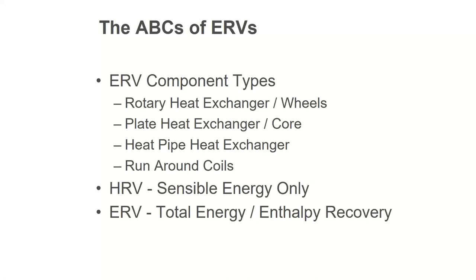So there are two types. There's HRV and ERV. HRV is heat recovery ventilator, sensible only energy, no latent. Latent's not my problem. I don't do moisture. Then there's ERV, enthalpy recovery ventilator. I do sensible plus latent energy. So obviously I want to do both when I can. There are some projects where you're going to want to do the HRV. Those projects are ones where the indoor humidity is regularly worse than the outdoor humidity. What do I mean by that? Well, if you're doing a locker room at a fitness center, you're generating a lot of water with those showers.